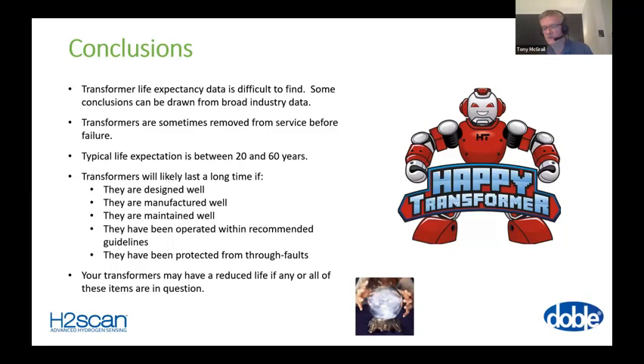Well, let's look at the rest of the population. For each of those, we need to treat them as an individual. For each transformer in our population that we're interested in, we have to collect data. We have to analyze the data and then see whether there is any failure mode in operation. And then, consequent to that, how much life has been lost from the capability of the transformer. Monitoring allows you to update that more frequently. Monitoring allows you to detect both long-term failure modes and short-term failure modes.